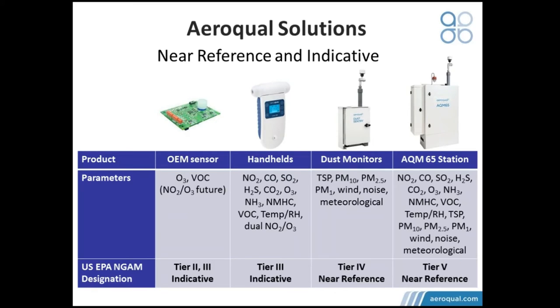As you can see from this table, one of our leading products is the AQM65 air quality station. It measures multiple gas parameters along with particles and meteorological parameters, including noise and solar radiation. This instrument would be termed a Tier 5 or near reference instrument. In some respects, its performance is similar to or exceeds that of a reference station. However, it uses some new technologies which are not currently listed under the US EPA as a reference or designated reference method.